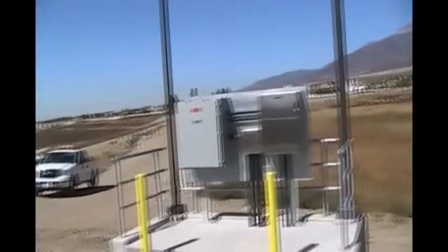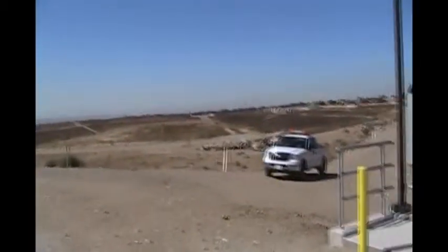This is part of our groundwater recharging system, and it has the same communications as the others. This one communicates back through RP4 to RP1 for the SCADA communications. There is a second panel on basin number 5, which controls sending out the analog signal and the intrusion alarm from that panel back here. That's the top antenna there. The bottom antenna is our communications to the SCADA.